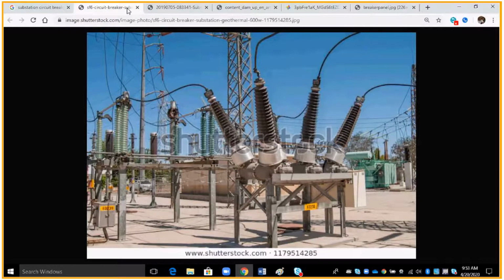Alright, so if you don't remember, need a little hint here. These are current transformers. To be able to get a signal from the primary going in and out, or take a measurement of how many amps there are going in and out, I need to transform that current from a high current level to a lower current level, so I'm able to take a reading on it. So that's what these are, current transformers. I'm transforming a very high current that's on the primary or transmission circuit, and I'm transforming it to a much lower one, and after it leaves here and is transformed, it goes into this panel. There I'm able to use that low current on a much smaller wire, take readings off of it, and be able to open and close relays, and eventually open and close the breaker itself. So that's the purpose right there.